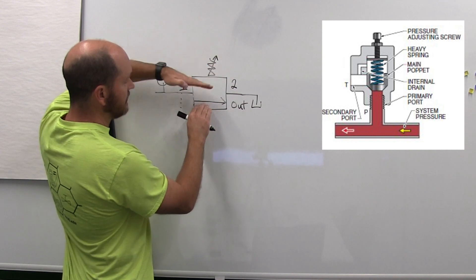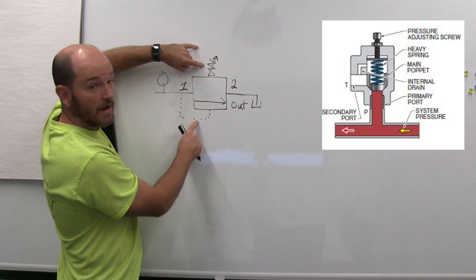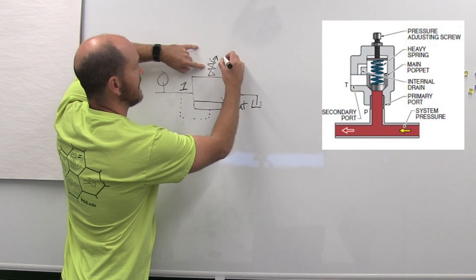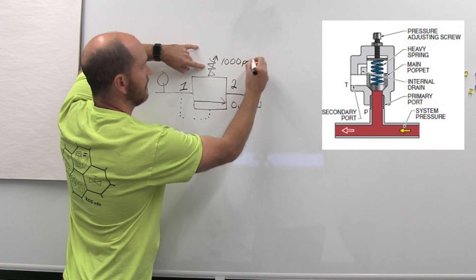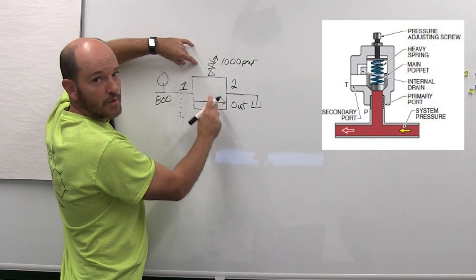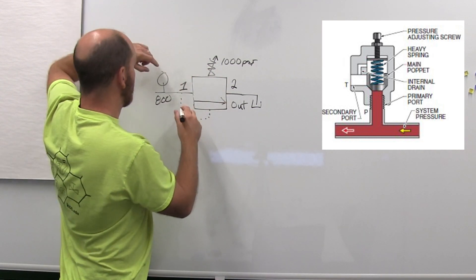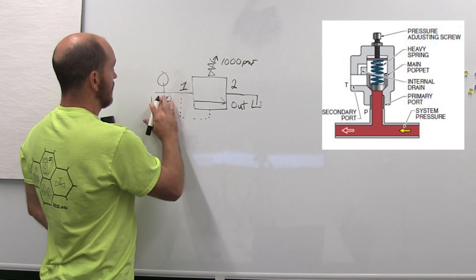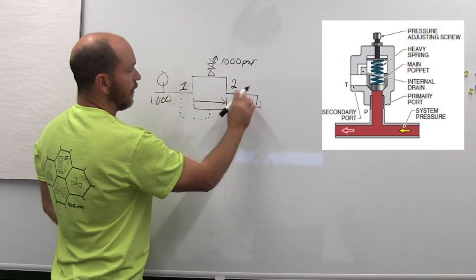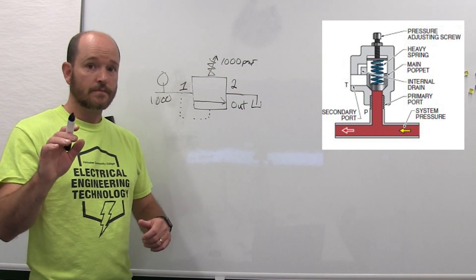This poppet is going to be balanced out by the comparison of the spring and the hydraulic pressure. If my spring pressure is set to a thousand psi and I have 800 psi here, this will be closed or only cracked open. But if this is at a thousand psi, this poppet would move up and oil would be allowed to go back to tank.